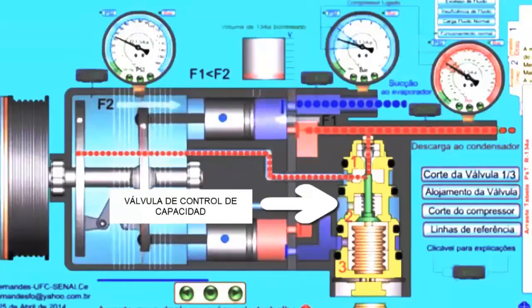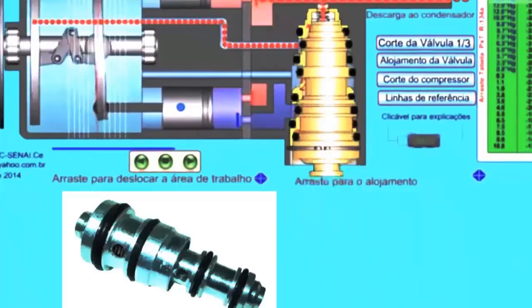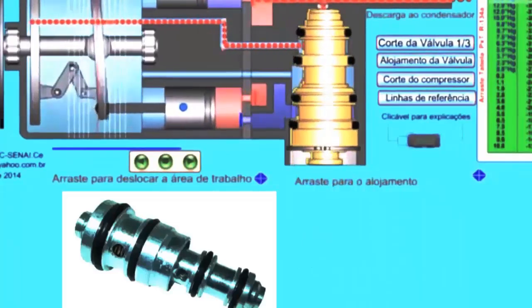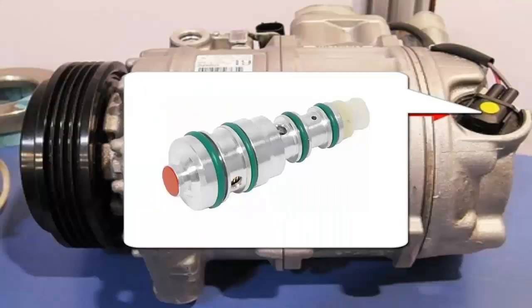To do this, the system's refrigerant must be recovered and the regulation valve, which is often accessible externally on the compressor, can be replaced. In some models, it is not necessary to remove the compressor from the system.